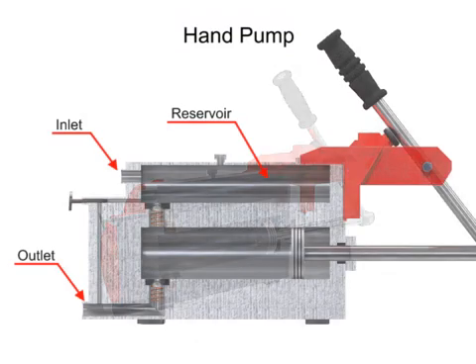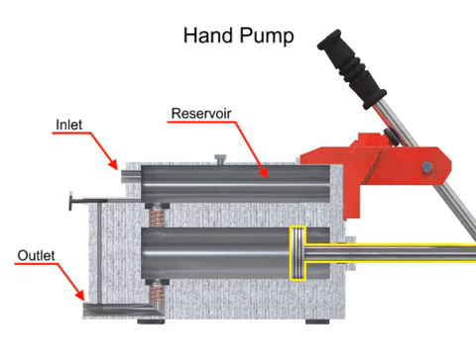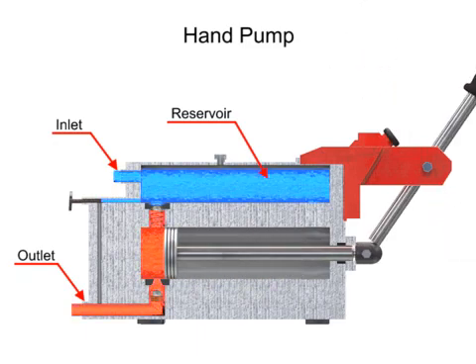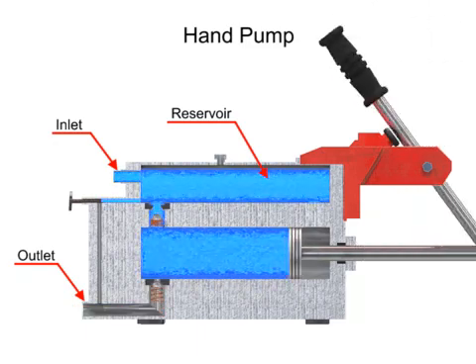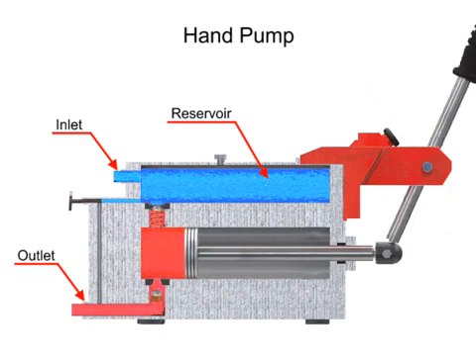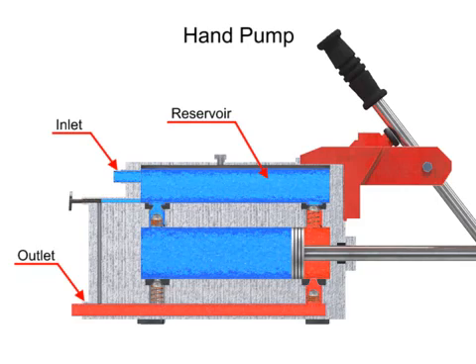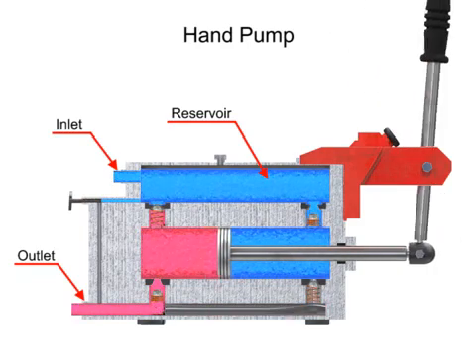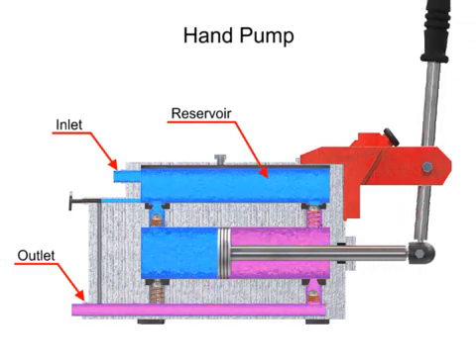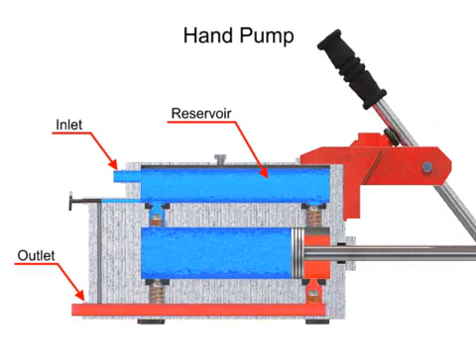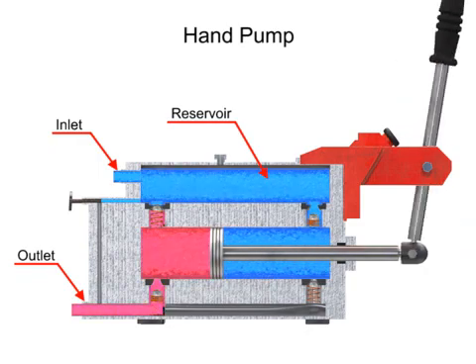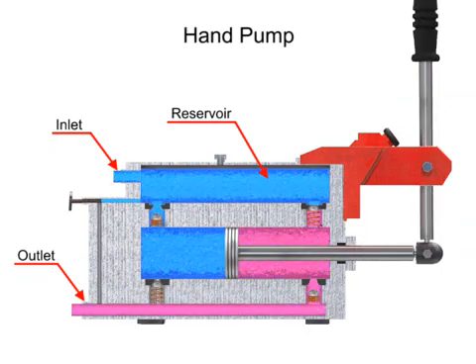Hand pumps are always of piston type and are usually constructed with a piston working between two check valves. Double acting hand pumps are more efficient, allowing fluid to both enter and discharge on both strokes of the piston. Moving the pump handle in either direction allows fluid to be drawn in from the reservoir and discharged via the outlet ports.